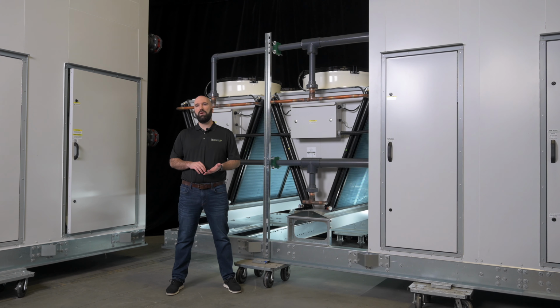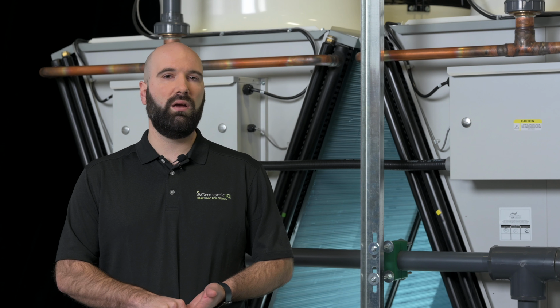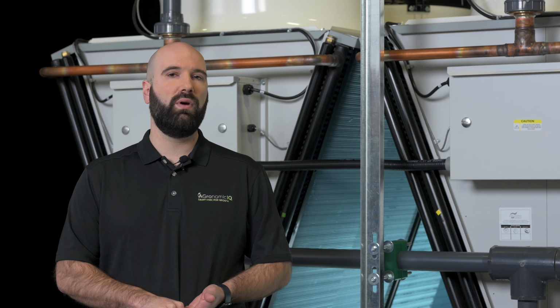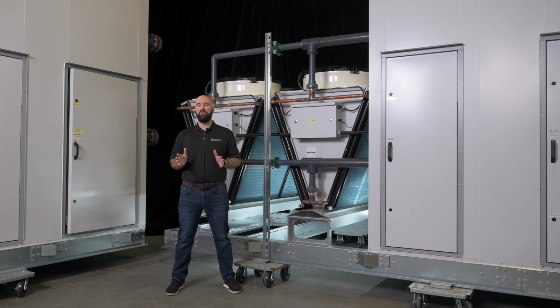But 2 is using a water glycol mix for heat rejection allows us to entirely isolate our compressor circuits from the outdoor ambient condition, which means that we can operate reliably in any outdoor ambient condition down all the way to -40 degrees. And that's a real boon in this industry, particularly because standard HVAC equipment in the low ambient condition really starts to struggle, particularly when you're looking at condenser-based units with reheat, because you end up with multiple condensers and a flooded condenser problem and liquid slugging and low pressure trips as a result. There's a variety of bad things that happen to refrigeration circuits in the low ambient condition, and having the glycol completely isolates that from happening.